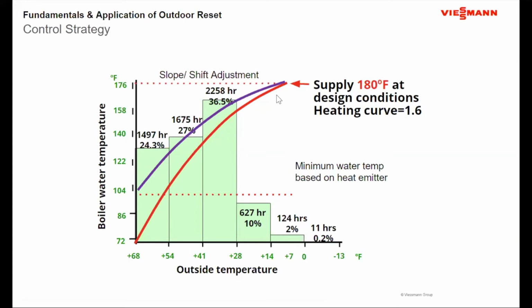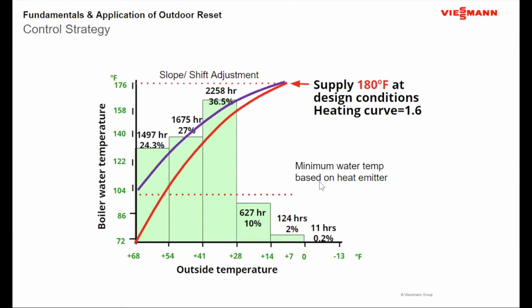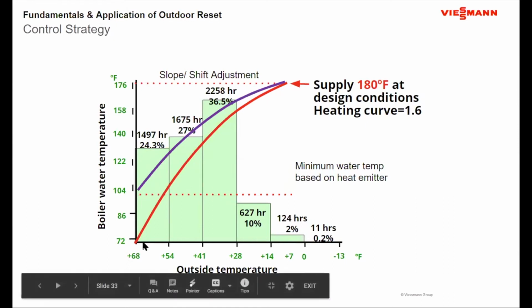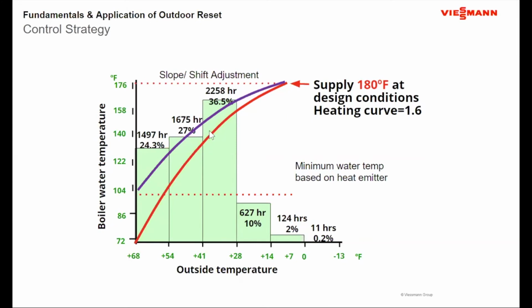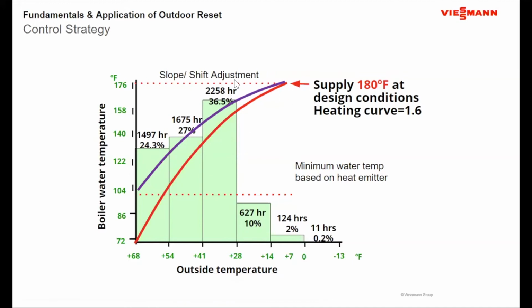Okay. So a lot of times you end up with a heating curve something like this. Really, the key is tying it in at the two identified points. What is the design water temperature under design conditions? I want that heating curve to hit there. And then what is the minimum water temperature that I want to achieve? Let's achieve that somewhere usually around a 65 to 68 degree day. And those 2 points do define the heating curve itself. Because ideally, for us, we always like to identify it through a slope, a 1.3, something like that, a 1.6. But with a heat emitter requirement, it really becomes, let's look at it and identify the two ends of the curve, those 2 points, based on outdoor temperature and water temperature, and then let's connect the dots between the two. And we'll see this listed as a slope and a shift adjustment on the control.